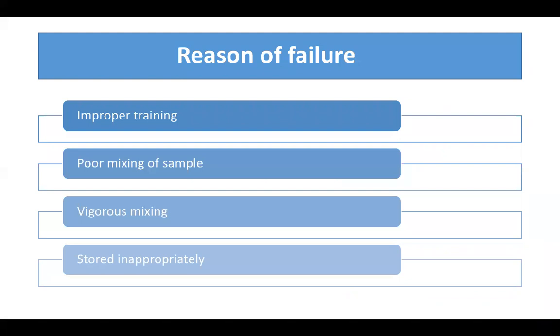And what were the reasons for failure? We analyzed. One thing may be improper training or poor mixing of sample, or too vigorous mixing, which is causing hemolysis, or samples are not stored properly.